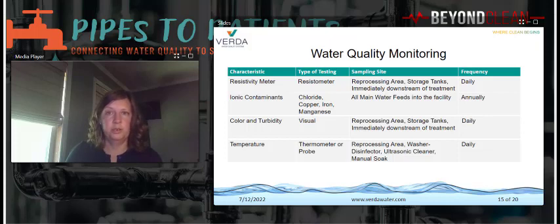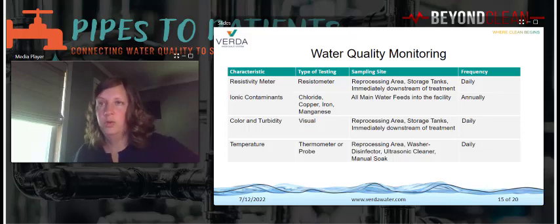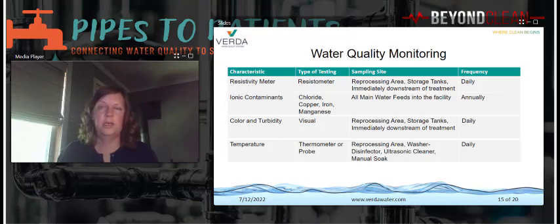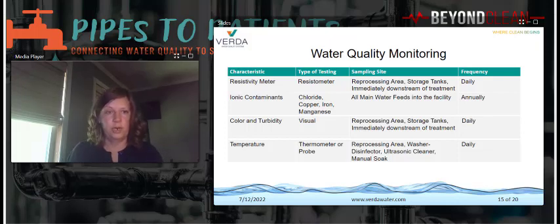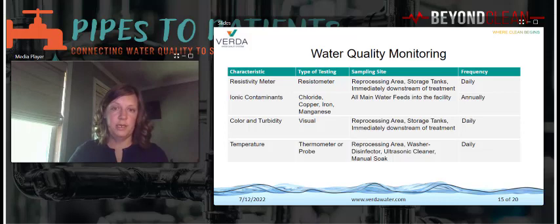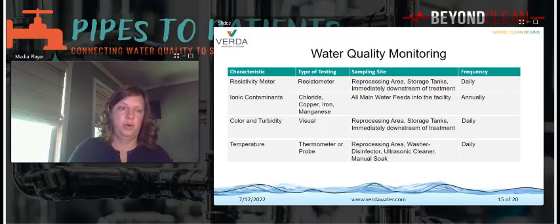The feed water to the boiler generating the steam for sterilizers should be monitored daily. The testing can be performed manually or using inline meters to track the measurements. Some tests, however, should be performed immediately to maintain accurate readings. This includes pH and total chlorine. The recommended holding time for pH and chlorine is 15 minutes. So if you're testing for those parameters, those should be done on site immediately after the sample is collected. The longer those are exposed to air, the more inaccurate those results will be.